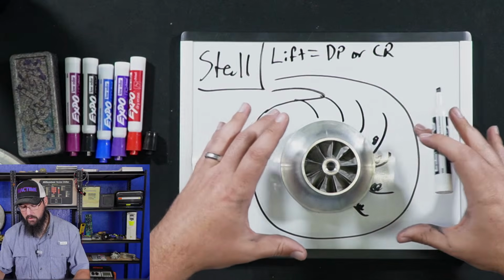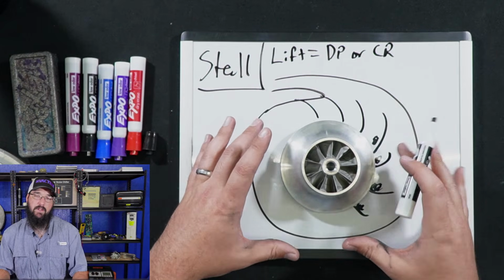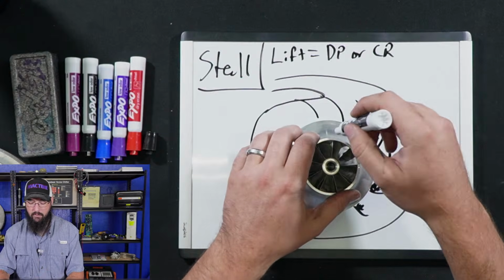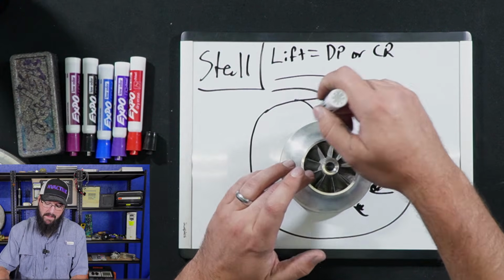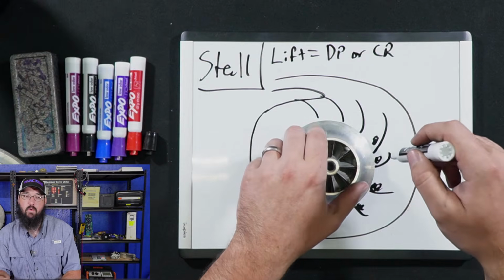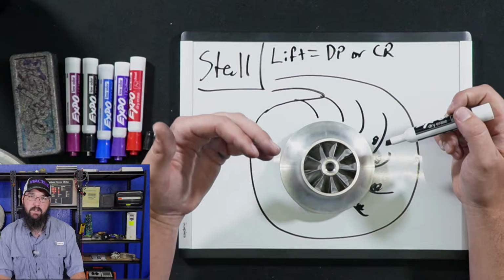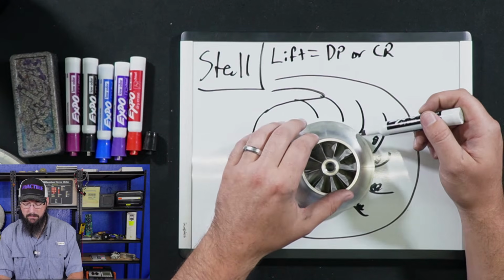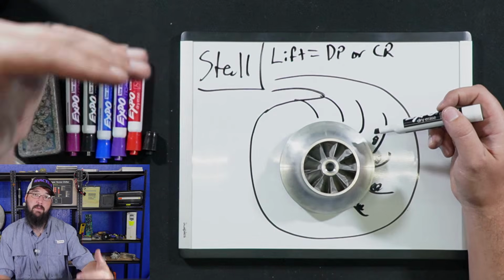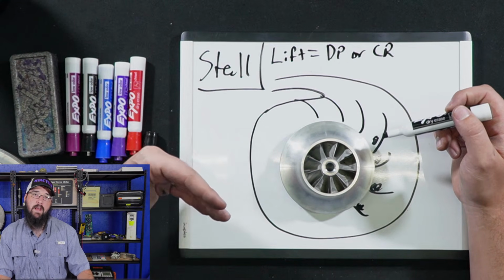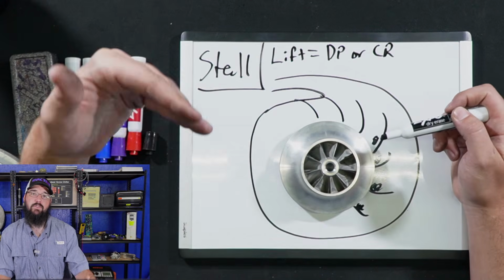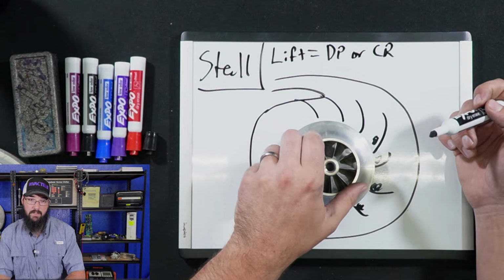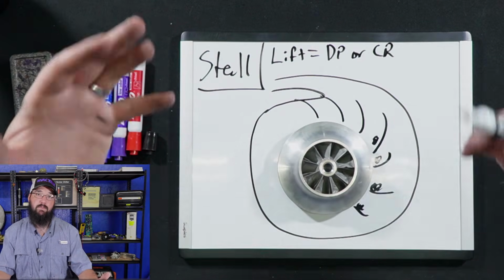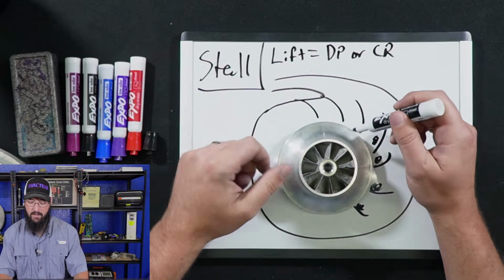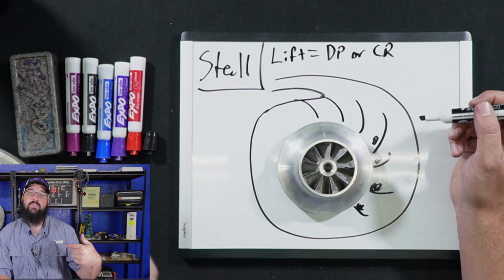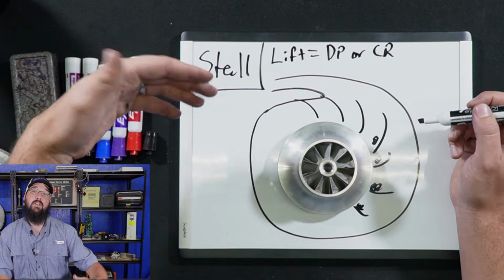So when we talk about stall, that's what we're referencing, and then we have the surge, and we have our surge line. So getting back to tip speed, there it is. As we're running slow, if we have a variable speed impeller, as the impeller slows down, our tip speed slows down, which means the amount of lift we can manage reduces. So that's why when centrifugals go into a surge condition, if they're variable speed, they will speed the impeller up. They'll increase speed. What they're doing is increasing the tip speed coming out of the impeller, which gives us the ability to overcome a higher level of lift.